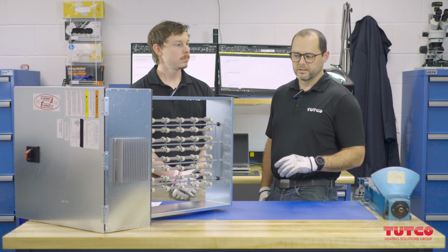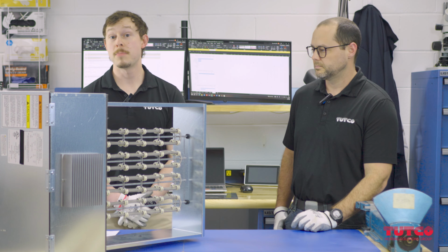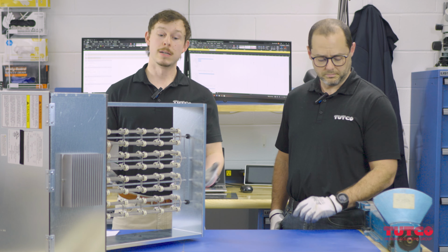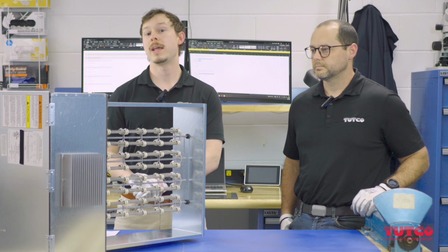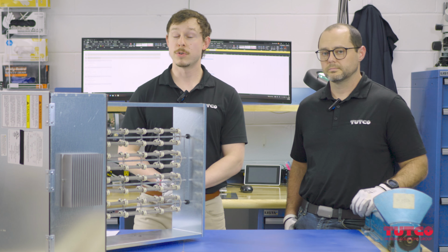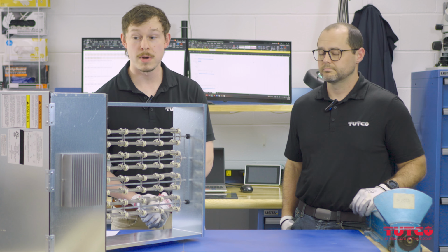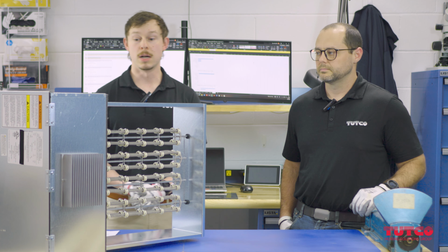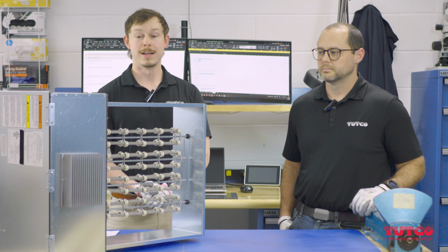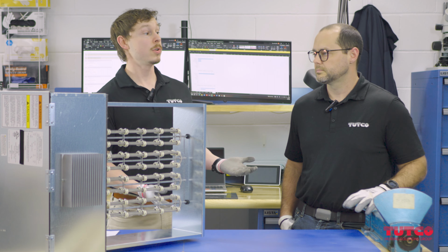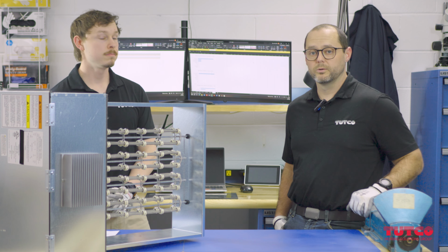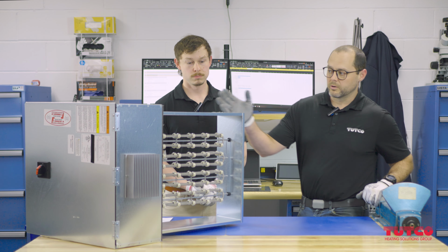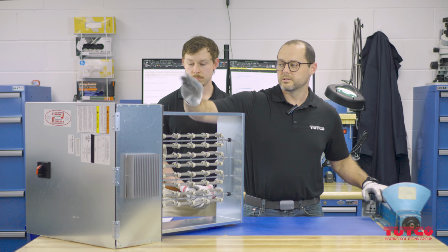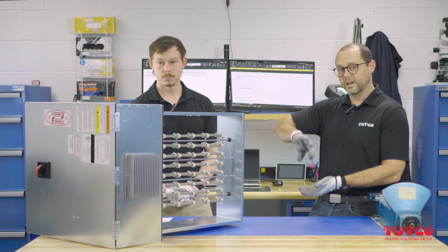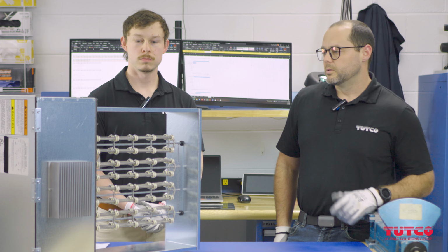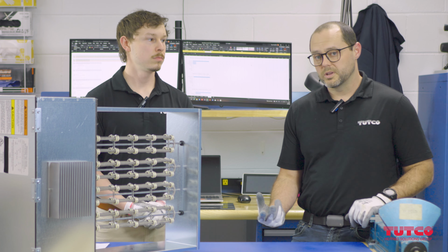The E-Series heater is one of the most versatile heaters on the market. If you happen to be on a job site and realize you've got a left hand or a right hand heater, fortunately with the E-Series you don't have to worry about that, because it can be flipped in a multitude of ways, even for vertical duct. Vertical airflow, horizontal airflow, the panel can be flipped left or right, or up or down in a vertical orientation. The only way it can't be mounted is in the bottom of the duct.